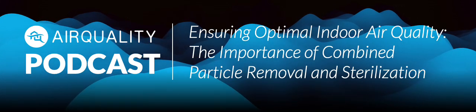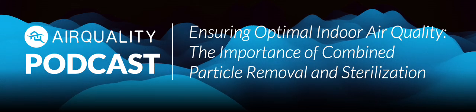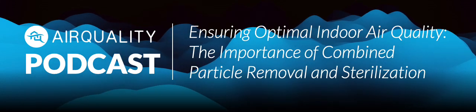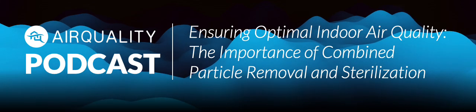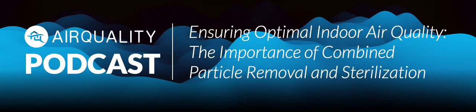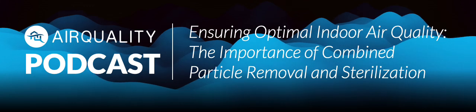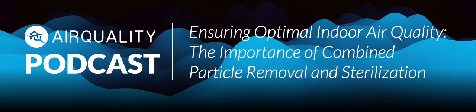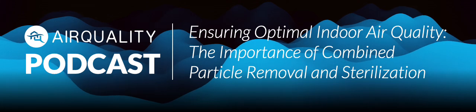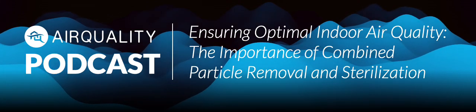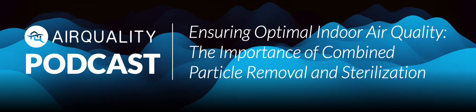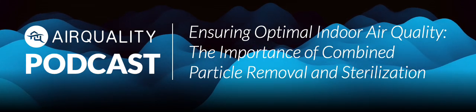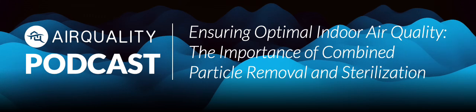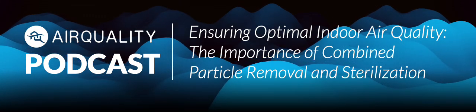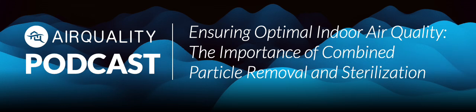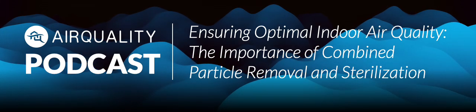And under what conditions does this immobilized threat turn into a reservoir? We're talking about environmental conditions that are common in almost any HVAC system, especially sustained warmth and high humidity. If the filter is dense, say a MERV 16 or a HEPA filter, it captures moisture very efficiently. So when that filter media gets damp and warm, those trapped, viable microorganisms have the perfect incubator. The filter essentially becomes a localized reservoir for microbial survival and growth. So instead of an air cleaner, we've accidentally designed a potential bioreactor right inside the ventilation duct. That's a great way to put it.